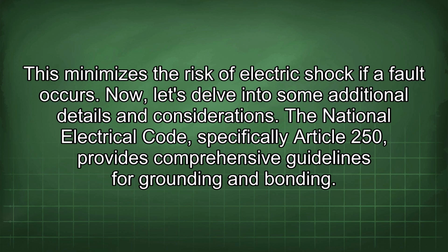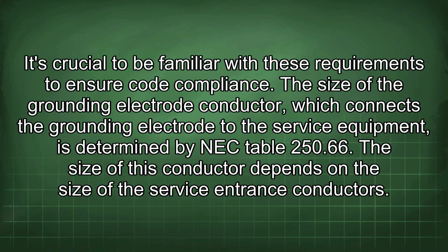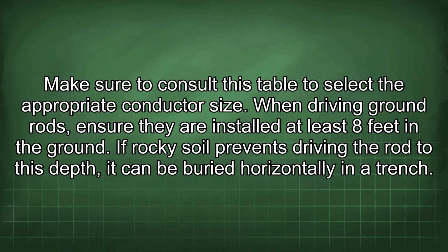Now let's delve into some additional details and considerations. The National Electrical Code, specifically Article 250, provides comprehensive guidelines for grounding and bonding. It's crucial to be familiar with these requirements to ensure code compliance. The size of the grounding electrode conductor, which connects the grounding electrode to the service equipment, is determined by NEC Table 250.66. The size of this conductor depends on the size of the service entrance conductors. Make sure to consult this table to select the appropriate conductor size.